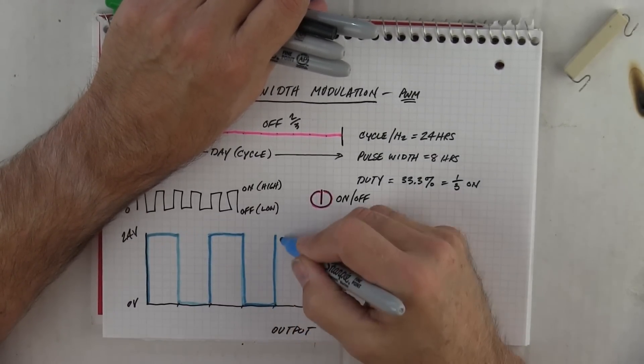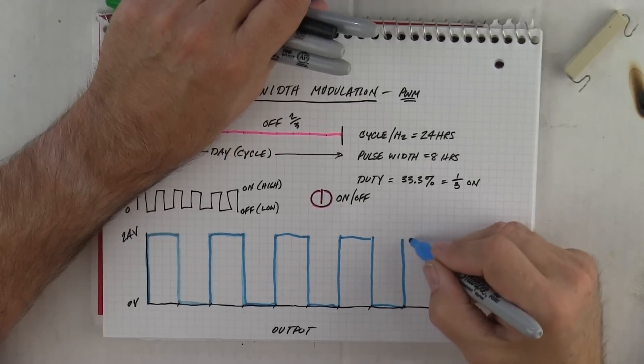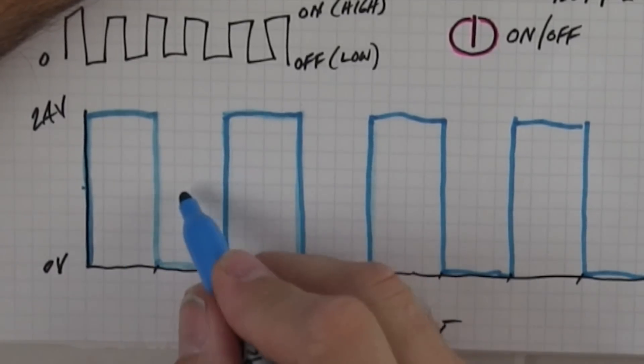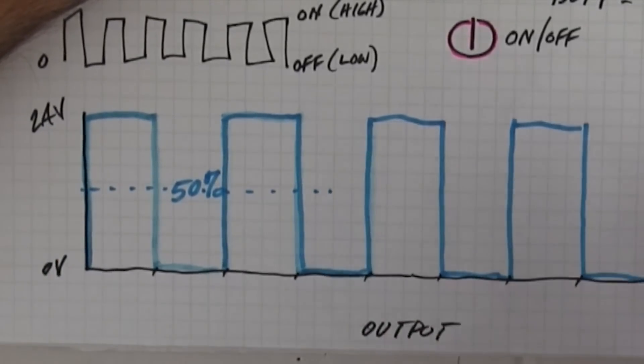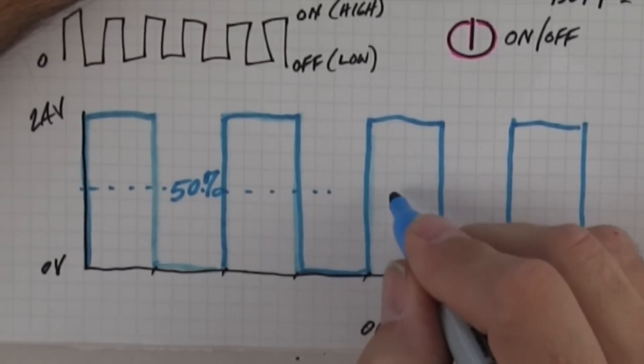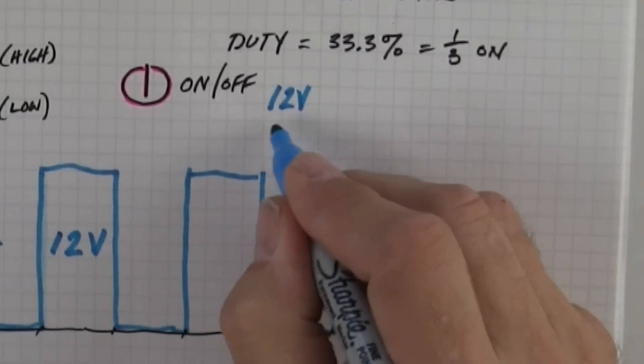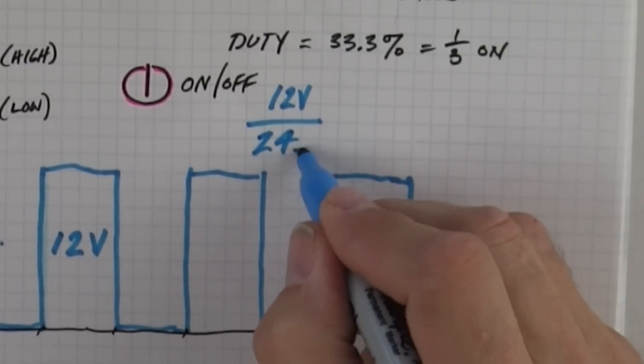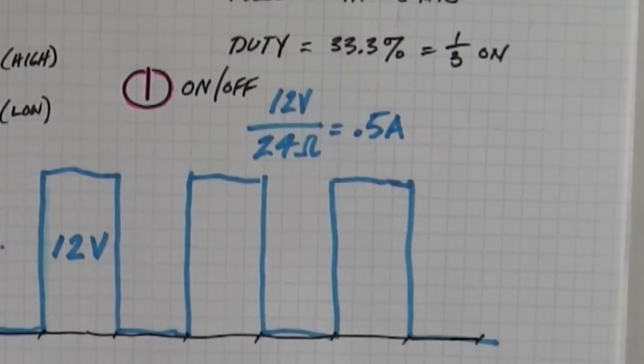I've got a 50% duty cycle — on 50%, off 50%. What is 50% of 24 volts? At 50% duty cycle the average voltage is 12 volts — remember, we're dealing with average voltage. Now let's apply Ohm's law: 12 volts with a 24-ohm solenoid on a 24-volt system means at 50% duty cycle the current flow through the solenoid is going to be 0.5 amps. That's just Ohm's law — that's why you need to know it.